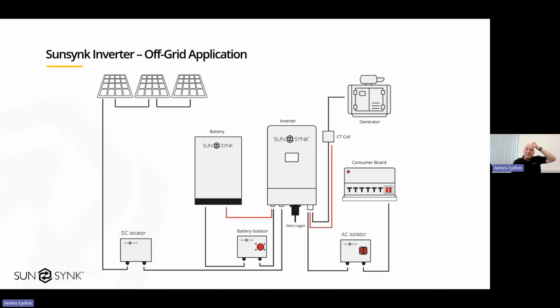And on the generator settings page on the inverter, there's a tick box to say that you've connected the generator to the grid terminal. So if you imagine that grid terminal is going to be looking for between 47.5 and let's say 51.5 hertz, whereas that Jenny is going to be outside of those parameters quite a lot while it's starting up. So by ticking that generator connected to grid, what that's doing is it's widening those tolerances. So yeah, quite flexible.